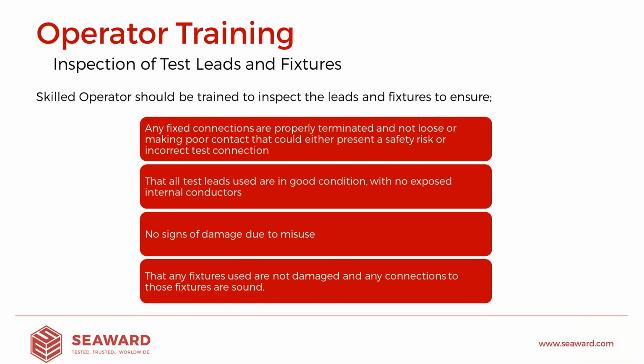Now, getting on to more skilled tasks that an operator should be asked to do. Again, at regular periods, they should be trained to inspect the leads and fixtures. And by doing that, we're looking for any signs of wear and tear within the testing circuit that could either impair the measurement or ultimately lead to an unsafe test connection. So things like the connections, are they properly terminated? There's no loose strands, the cables aren't over time being stressed and maybe being pulled apart, and therefore we're starting to see the inner conductors. Any signs of damage due to misuse.